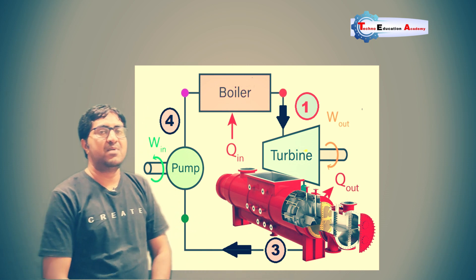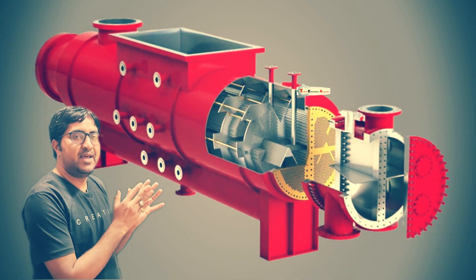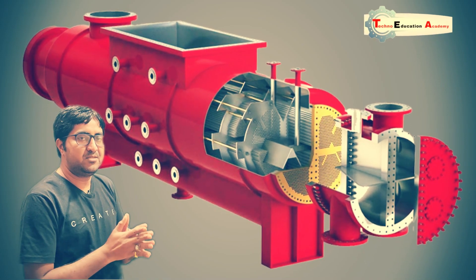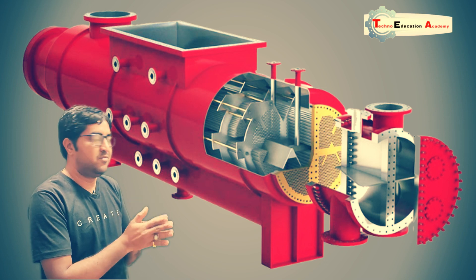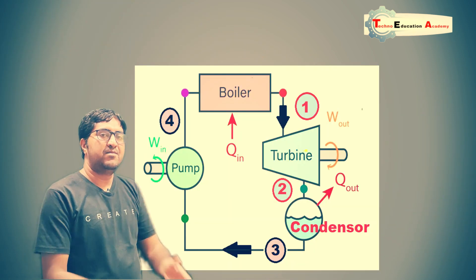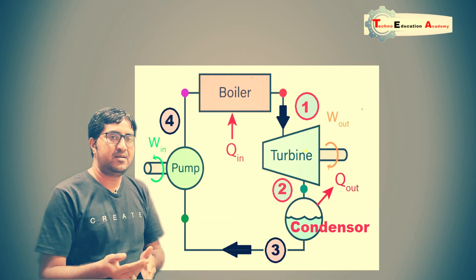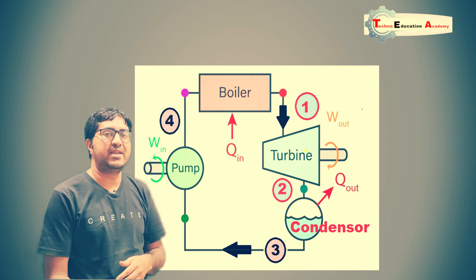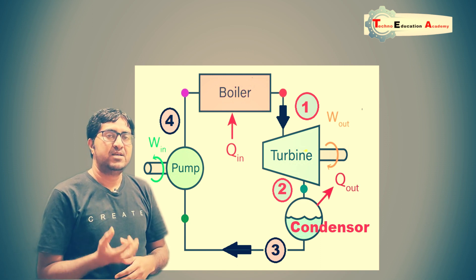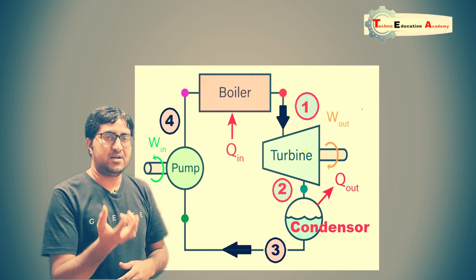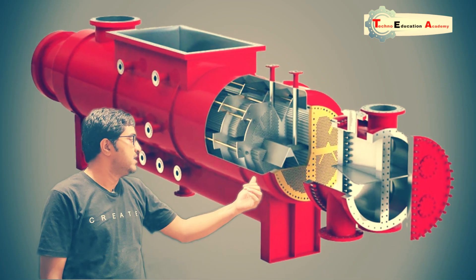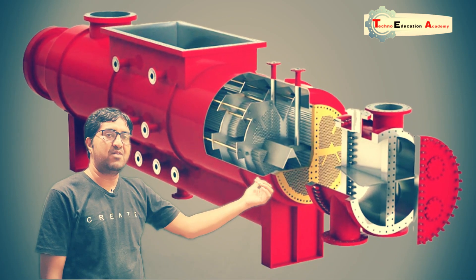The importance of the condenser is that a negative pressure, or vacuum, is maintained inside it. Vacuum means pressure below atmospheric pressure. This vacuum is needed because if air is present inside the condenser, it creates back pressure on the turbine blades, which reduces the work done by the turbine. So the first need of the condenser is to maintain vacuum continuously, 24 by 7.